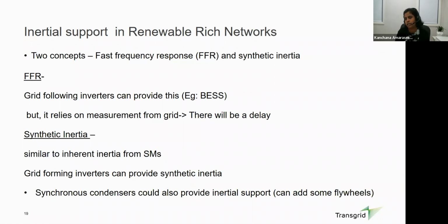Then again, we have the same question. If in traditional networks these services are provided by synchronous machines, what happens when it comes to renewable networks? Here I wanted to discuss two concepts. The first concept is synthetic inertia. As I mentioned, things like grid forming inverters can provide synthetic inertia, and it is faster. However, there's the second concept called fast frequency response, which depends on the frequency measurement from the network. Basically, it gets the frequency measurement from the grid and tries to respond with the appropriate active power. Usually grid following inverters can also provide these services, but it depends on whether they have any headroom. Batteries usually can provide fast frequency response services.